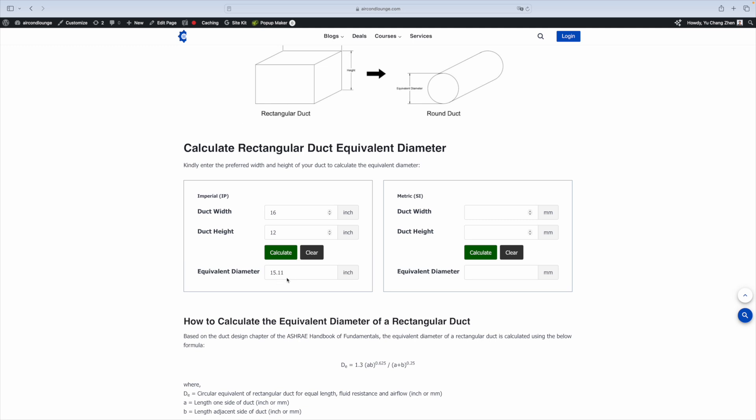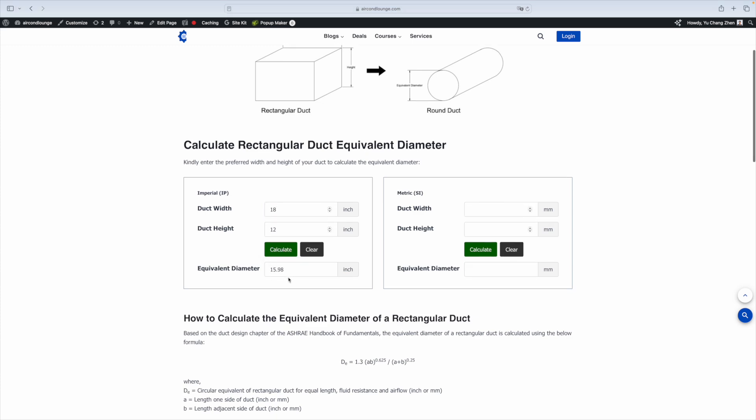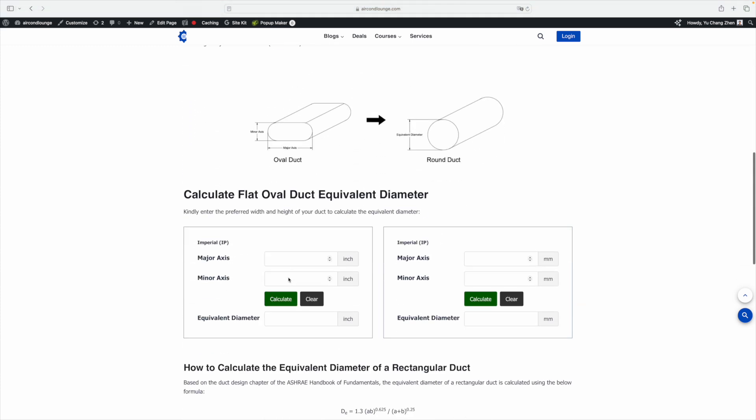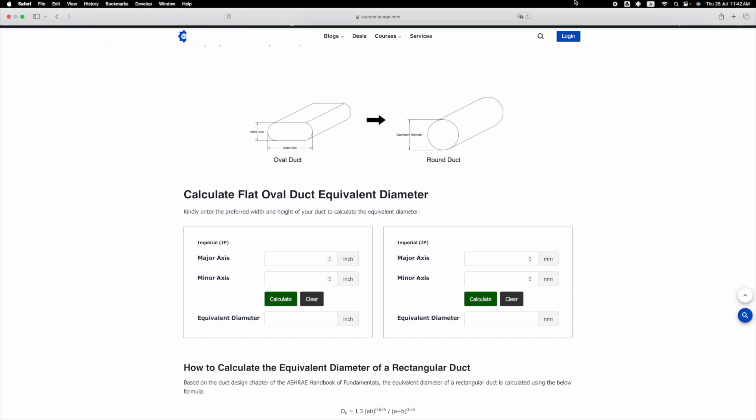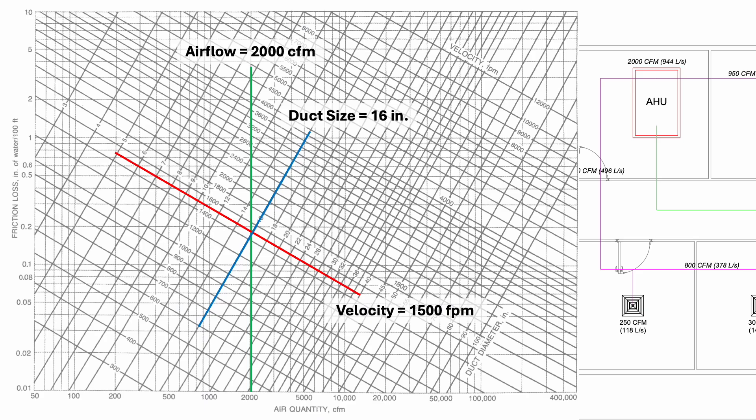Now, the equivalent diameter we get is 15 inch. What we need is 16 inch. So, we increase the duct size until we get it. We can also do the same for other ducts. You can find the link to this equivalent diameter calculator in the video description. The corresponding friction loss is 0.18 inch water gauge.